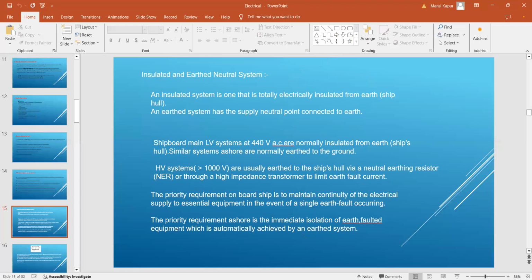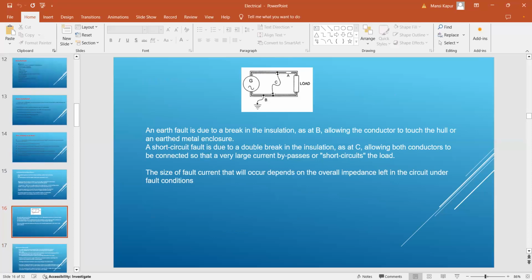The priority requirement on board the ship is to maintain the continuity of the electrical supply to the essential equipment. What are the essential equipment? Like your steering gear motor. In the event of a single earth fault, they should keep on running. The priority requirement ashore is the immediate isolation of the earth faulted equipment, which is automatically achieved by an earthed system. Understood? Yes, sir. Okay. Now look at this diagram. One earth fault has occurred at point B and another at point C. Now we will see what they are saying.